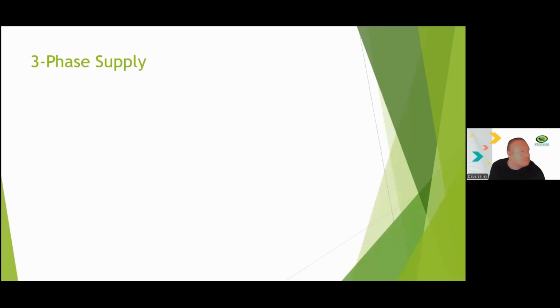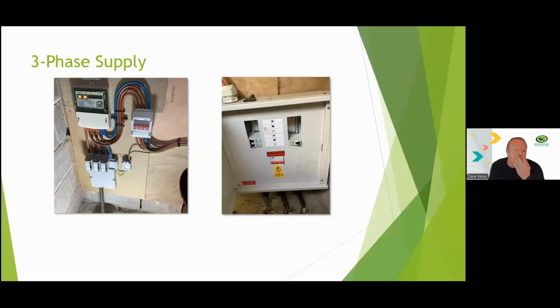The other thing to look out for, it's quite unusual, but some domestic properties have a three-phase supply. Normally you'll see this in commercial properties, but some particularly larger houses do have them. It's essentially three supplies that have been combined together, and you can see in this example there are three fuses as it comes in, and then usually you'll see a distribution board here. That's because the supply can be split into three, like normal supplies. If you've got a big house, you might have an east wing, west wing, center, for example. So you can split it, or it is possible to have equipment that uses the full three phases.